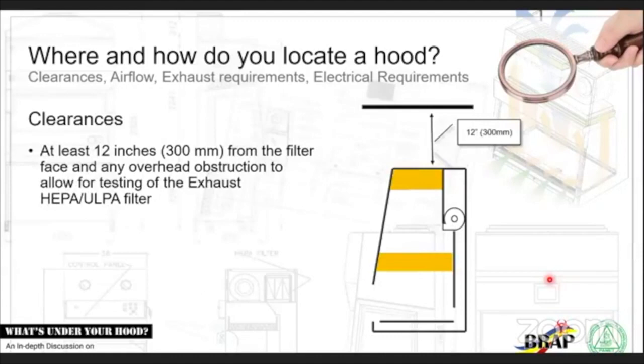Alright. Now, ceiling clearance. This is another one, a most common problem. There should be at least 12 inches of clearance between the top of your filter, or the access port of your filter if there's a structure here, and any obstruction on top. Again, not the ceiling, but any obstruction. Your ceiling may be here, but your water lines may be crossing here. Please avoid placing your biosafety cabinet under water lines. We don't want any electrical equipment under any water line, any plumbing lines. If those leak, goodbye. All right?